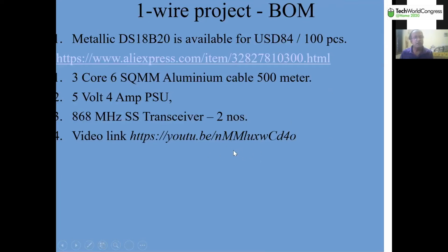And the major expenditure of this project is this 3-core 6 square millimeter aluminum core cable. You have to lay 3-core wires from the first sensor up to the last sensor, whatever the length. You have to have two 5 volt, 4 ampere power supply units, one at each end. This is called parasitic power supply. You can take power from the microprocessor end, but that way there will be a loss of voltage due to the internal resistance of the cable at the other end. So to combat that, we proposed to have 2 power supply units, and we have 2 power supply units.